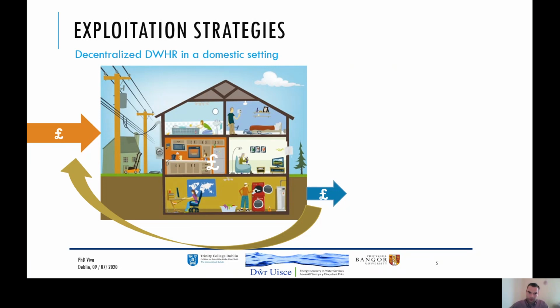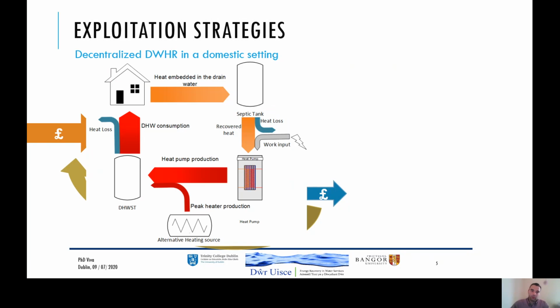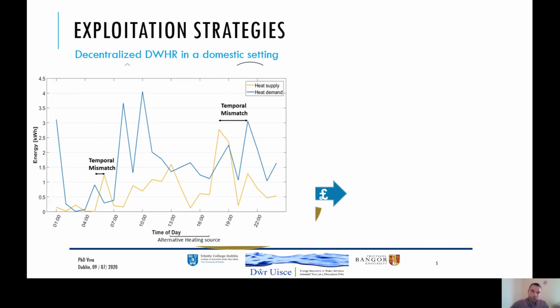building's energy consumption. In a domestic setting, we looked at the wastewater leaving the building with the embedded heat, and the wastewater was then collected in a septic tank or in a wastewater holding reservoir. From this holding reservoir, we recover the heat, and with additional electric work input, it's introduced into a heat pump, which then produces hot water. In case additional heat is needed, an alternative heating source, a peak boiler, is providing this additional heat. The hot water is then stored in a domestic hot water storage tank, from which it is then again consumed by the building. The specificity of this research was that we looked at the temporal aspect of the analysis.